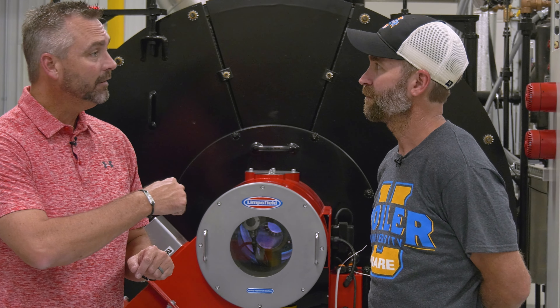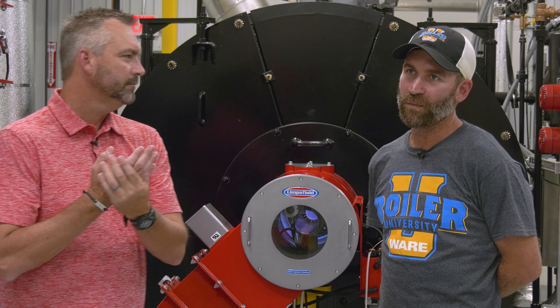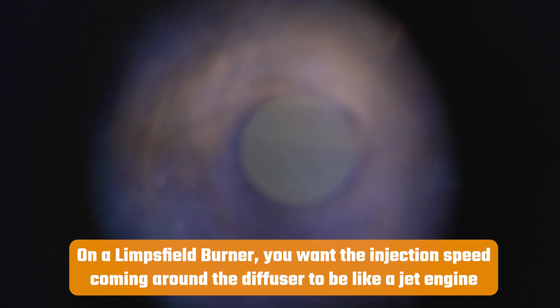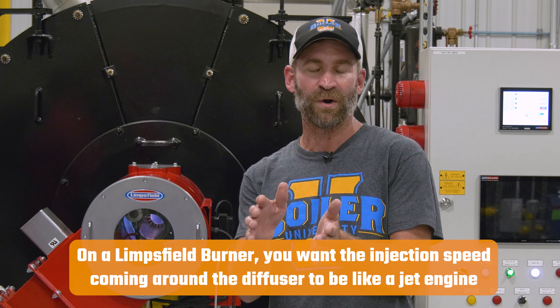From that point, you would walk around to the back and actually look at the flame. From the back, on a low fire and the main flame ignition on a Limpsfield Burner, you're looking for a blue core with yellow tips. You don't want to see too much yellow — just enough yellow at the end. And it shouldn't be swirling real lazy; it should be a nice steady flame shooting out of the burner.